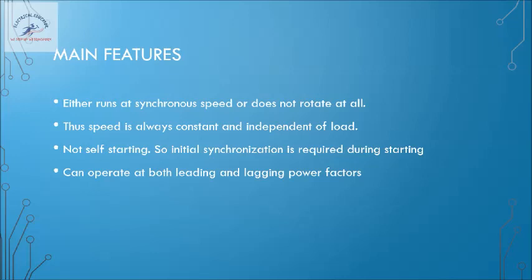So this synchronous motor is the only motor which can operate at both leading and lagging power factor. That means it can supply the reactive power or it can absorb the reactive power. So usually most of the motors operate at lagging power factors. The synchronous motor is the only motor which can operate at lagging, unity or leading power factors.